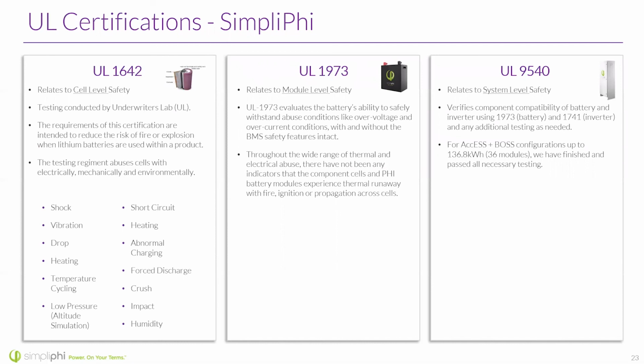As far as the UL specifications, we have UL 1642. This is cell level testing specifically. So it goes through things like shock, vibration, drop, heating, all of that stuff, on a cell level. UL 1973, the very big standard for a very long time, relates to module level safety. So this is battery level, that is what we would consider the battery level itself.